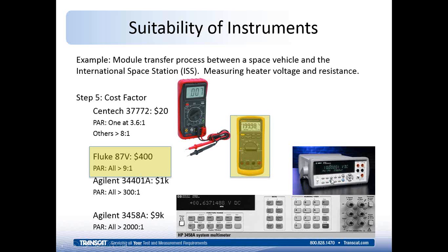The Agilent 34401, which is shown in the picture to the right, is a $1,000 instrument roughly, and all of its process accuracy ratios for this application are better than 300 to 1. So now the question is, if you want to spend 20 bucks, 400 bucks, 1,000, or $9,000 on the 3458, which are all better than 2,000 to 1. So clearly this last one doesn't make sense, and probably the 34401 is overkill for this application. So then it's down to the Centech and the Fluke 87. And do you want to spend 20 or 400?